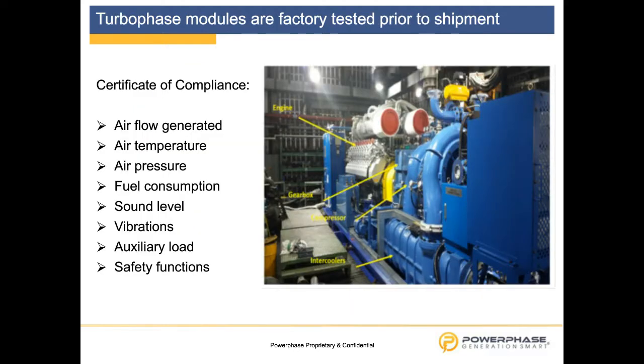I have mentioned before that the system is modular and factory acceptance tested. On this picture you see a screenshot of the test stand of our supplier, or rather our packager. The units are packaged in Korea. And here we certify several parameters that we guarantee commercially to the end customers. It will be the airflow generated, the air temperature and the air pressure, which are the main permissive signals for the compressor discharge.